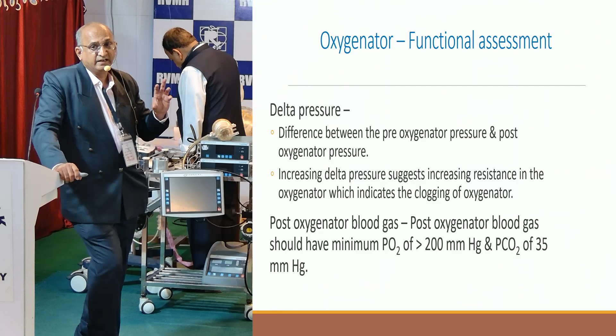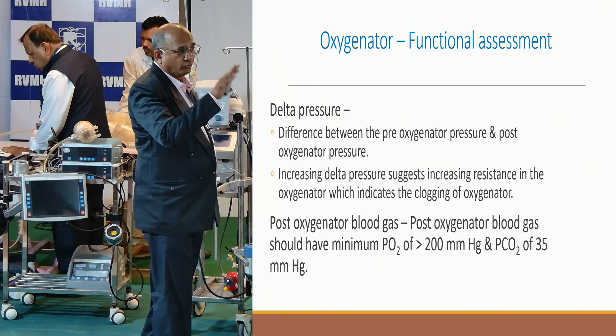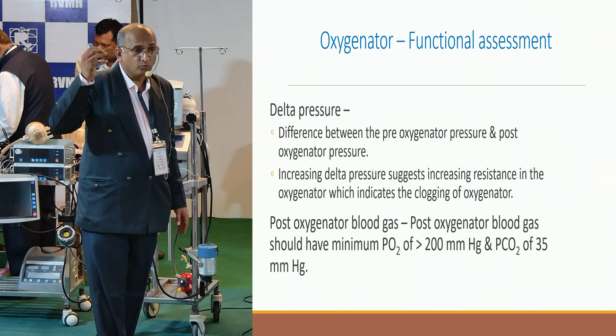So P2 is pre-oxygenator and P3 is post-oxygenator. Again, we measure these two pressures, and the difference between them is the delta pressure, which tells you about the oxygenator capacity. If the oxygenator starts getting clogged, your P2 will increase because it has to push with more force to pass through. Your P3 will decrease because there is a drop in pressure as it passes through a resistant membrane. So your delta pressure will increase.